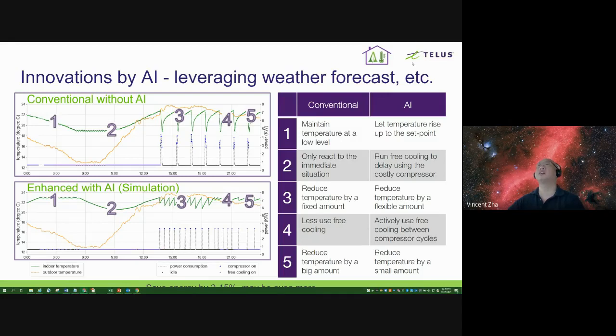This is in clear contrast to the conventional control on the top chart, where right from the beginning, the conventional control kept running the free cooling and pulled the temperature all the way down to a low level of 19 degrees and maintained it there.